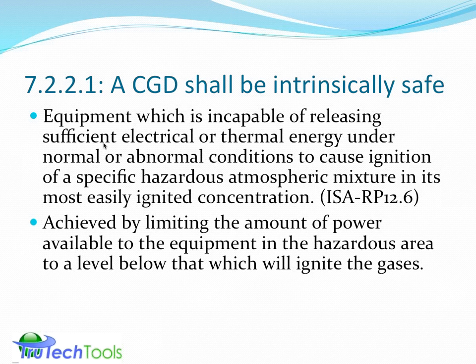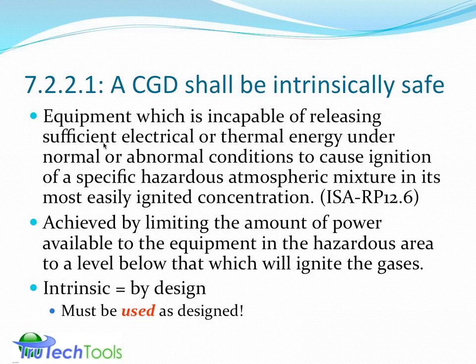So this is achieved by limiting power that's available inside the equipment. So it's done by design that makes it intrinsically safe. Other aspects of it are maintenance and replacement and service has to be done in a proper, certain manner. So these are all important things to keep the product intrinsically safe. So it's basically something that's inside the product, the way it's designed. It must be maintained and serviced in that way in order to keep it intrinsically safe. So it would comply with this statement for the standard.